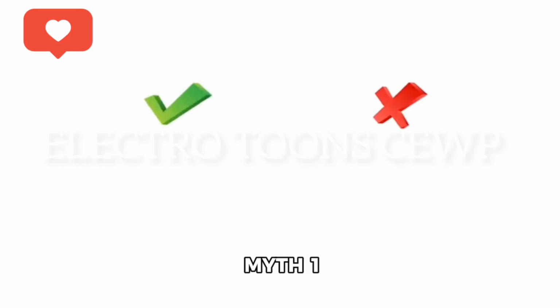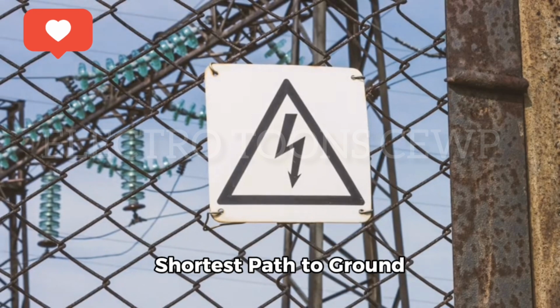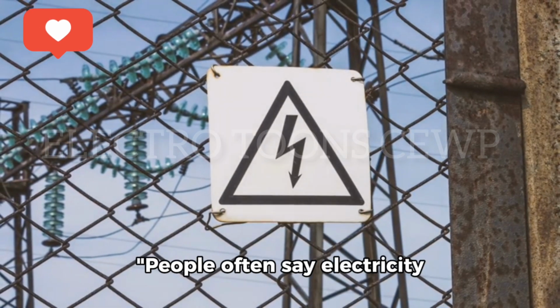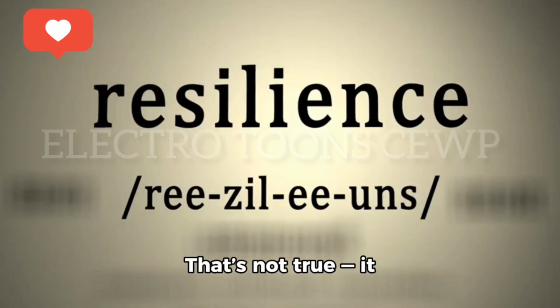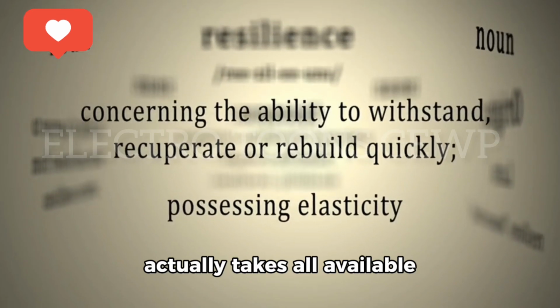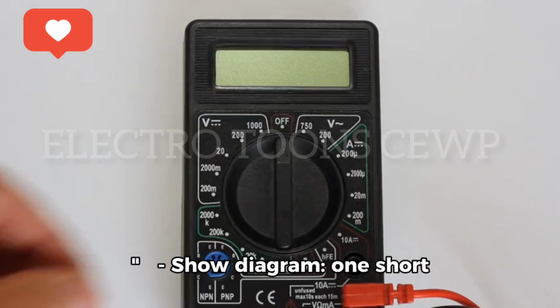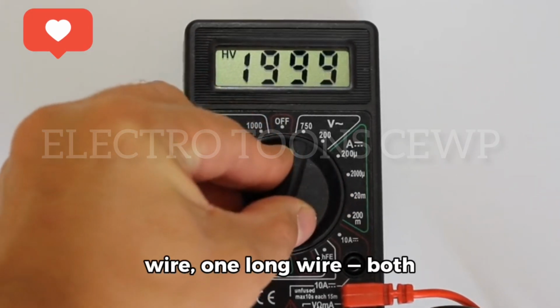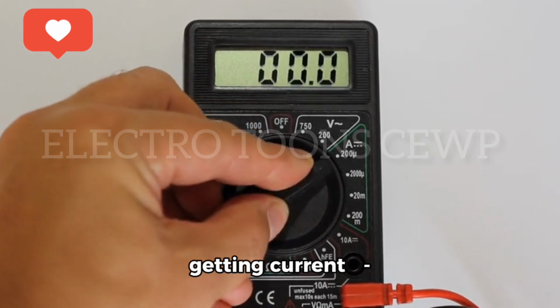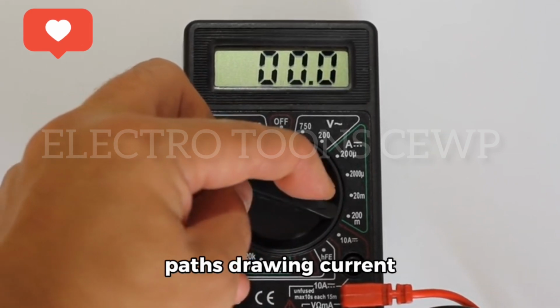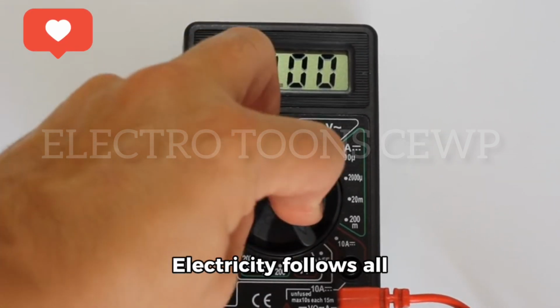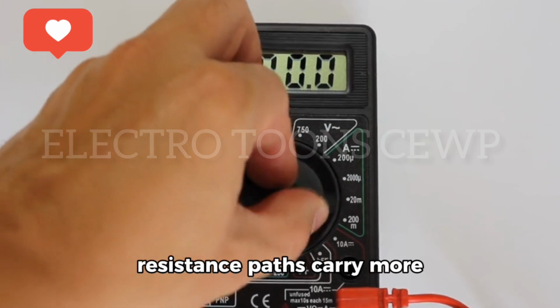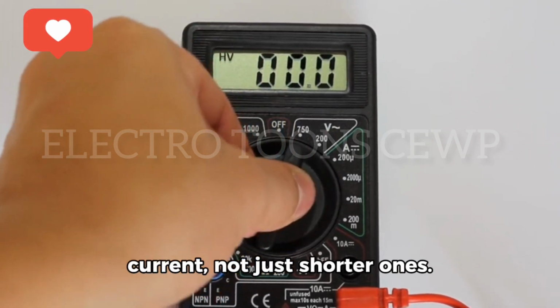Myth 1. Electricity takes the shortest path to ground. People often say electricity takes the shortest path to ground. That's not true. It actually takes all available paths based on resistance. Show diagram: 1 short wire, 1 long wire, both getting current. Multimeter showing parallel paths drawing current. Electricity follows all conductive paths. Lower resistance paths carry more current, not just shorter ones.